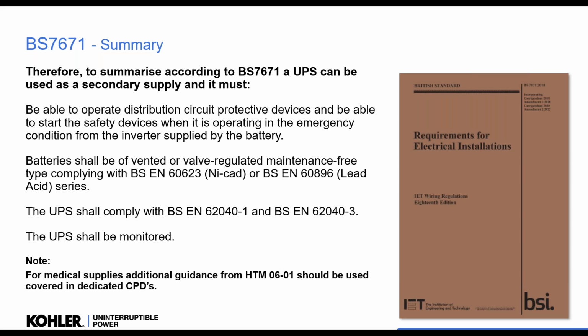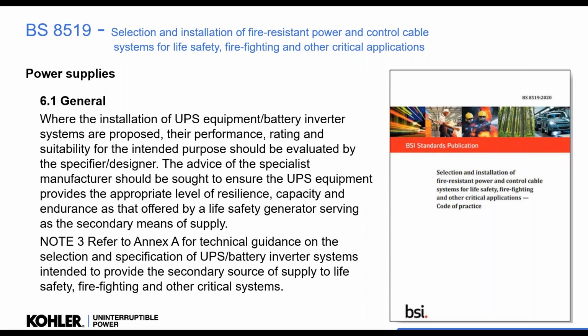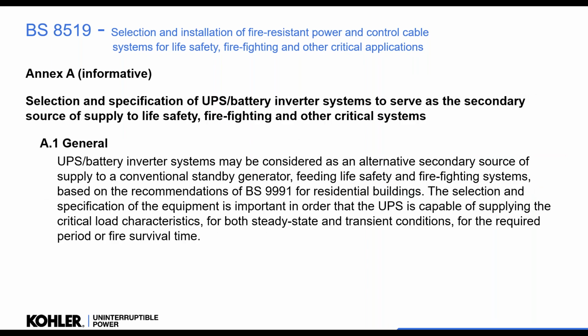Okay, so one of the regulations that was updated not too long ago, BS 8519, is causing us to have a lot of discussions with customers. It talks about the installation of UPS equipment or a battery inverter to be used as a power supply, as a secondary source for life safety, as an alternative to a generator or second supply. An Annex A has been added, and it talks about Annex A a lot and refers to that for technical guidance on the selection and specification of UPS and batteries. So that annex is very helpful, and it's referred to in other regulations.